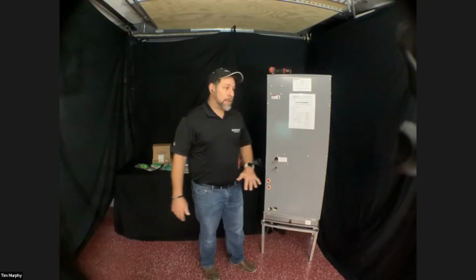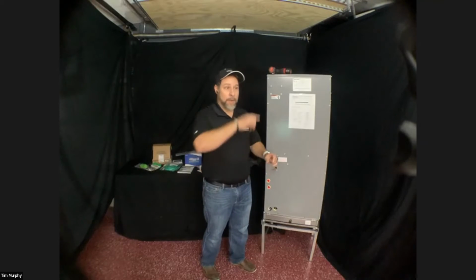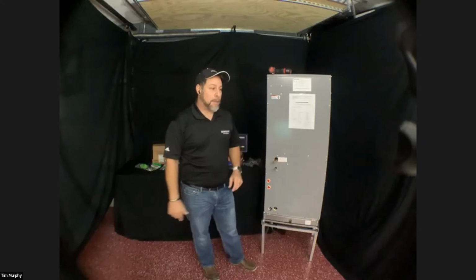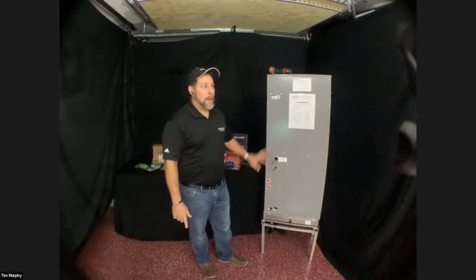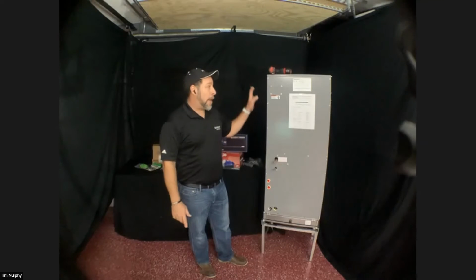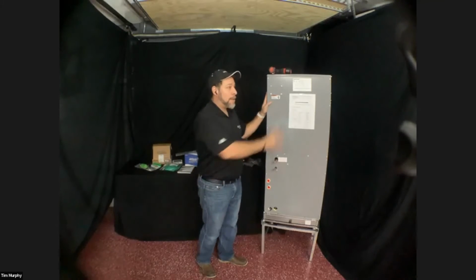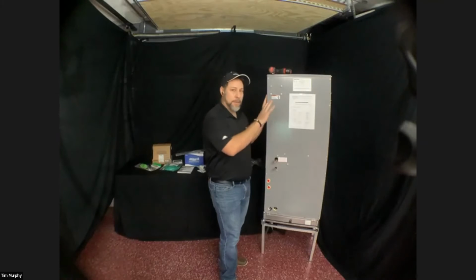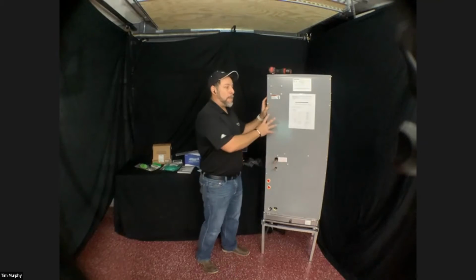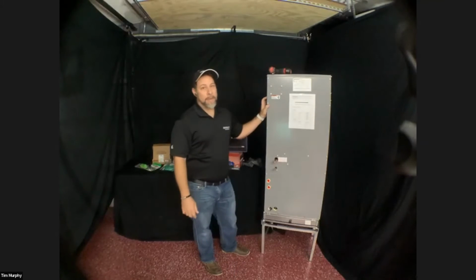They did have some ductwork on the return. So that thin filter that they had, of course, it was one of those crazy 3M filters. It doubled the static pressure on the system. Without the filter, I was at a 0.5 static total. Not on a Samsung. This was on a Ruud system. I was at 0.9. I took the filter out. I was down to 0.5.